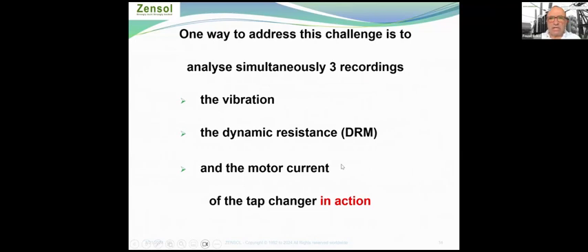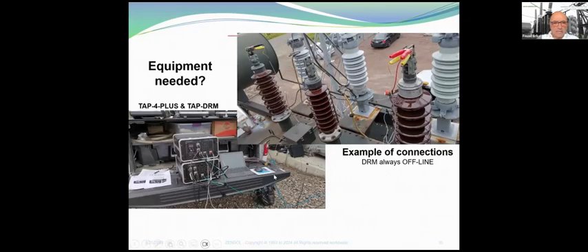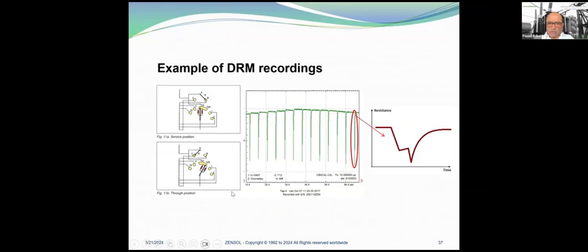So one way to address this challenge is to analyze simultaneously three recordings: the vibration, the dynamic resistance, and the motor current of the tap changer in action. So what we need is what we call a Tap 4+ with an accessory whose name is Tap DRM, and of course the transformer is totally offline. In fact, the Tap DRM is a current source.